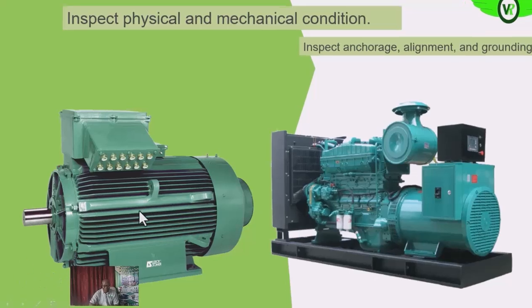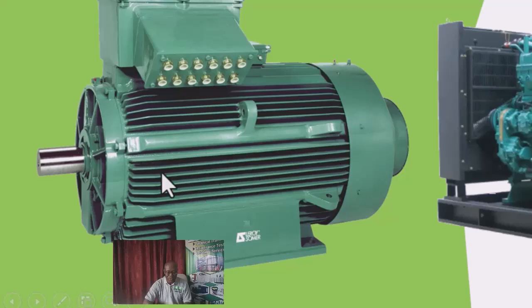Then on the electric motors too, you check to see that it is neat, these cooling fins, that there is no deposit or debris covering them or in them. If there is, you clean it up to ensure that the cooling air from the fan can flow freely through the cooling fins. If the cooling fins are blocked, that can increase the running temperature of the electric motor. So you want to check to see that they are free of debris.